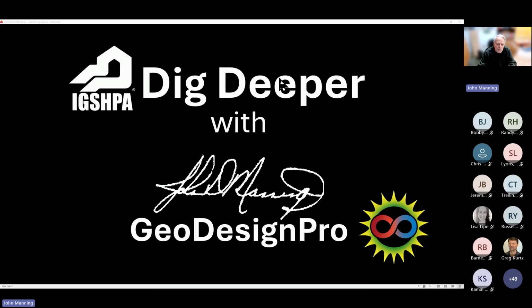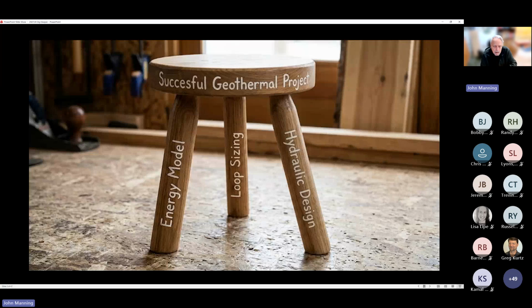Let me start off by reiterating what we have learned over our experience with the geothermal industry: a successful geothermal project requires three significant areas of engineering know-how. That includes energy modeling or load calculations: what are the loads that are going to impose BTUs to be extracted from the ground or rejected to the ground? There's also loop sizing, which in itself is full of parameters that have to be evaluated and calculated. And then the third leg, the hydraulic design. That's what our software is focused on. We're not sizing loops. We're not doing load calculations. It is that hydraulic design function that we have focused on.